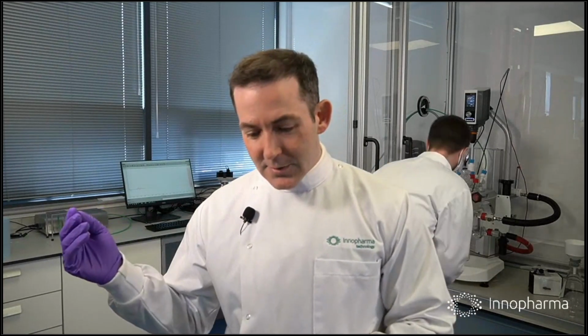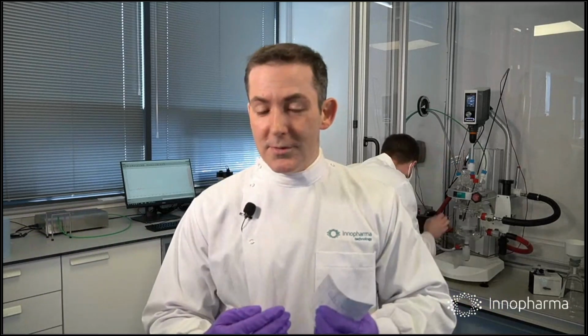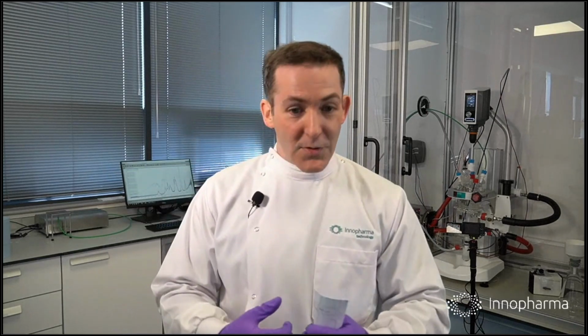Is there a lag? It cannot be truly real time. Now, other sensors such as the near infrared can be used. In fact, strictly speaking, the spectrum from any of these techniques, because there is an acquisition phase, an acquisition time, means that it's not real time. However, with chemometrics, the speed of acquisition is extremely fast in some of these detections. With near infrared, for example, you can get a detection on the order of 10 milliseconds, so quite fast indeed, very closely approximating real time. So the output signal needs to be characterized to be useful. Absolutely 100% correct. I'm glad you asked that question. We're going to talk about how that's achieved.